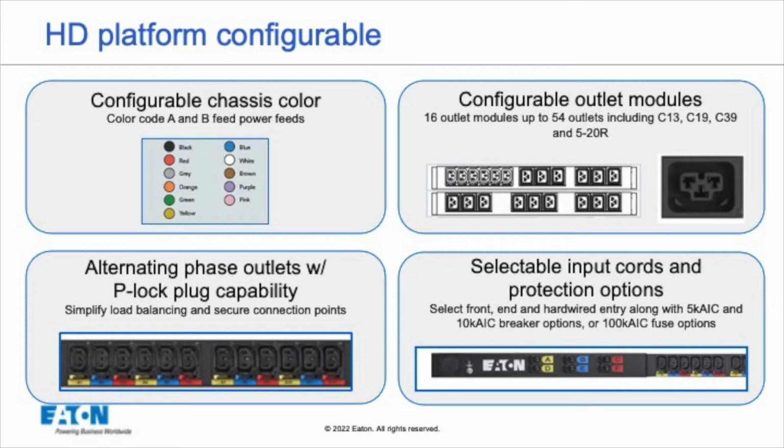So when you have your red cable going from server to your red PDU, blue to blue, if you look at the server, you can see it's got dual sources. You can trace that back. And if you have something plugged in wrong, like a red cable plugged into a blue PDU, it sticks out like a sore thumb. So it eliminates any risk of misconnecting a device to power feeds. That's why people like it.